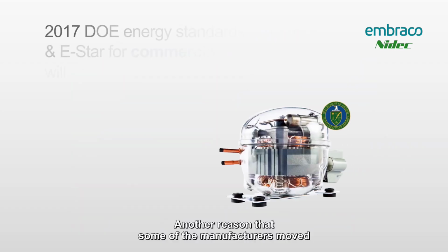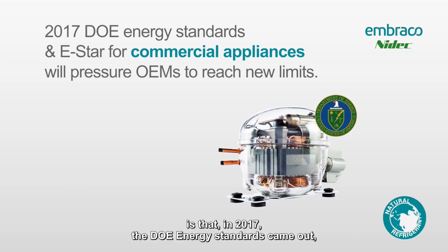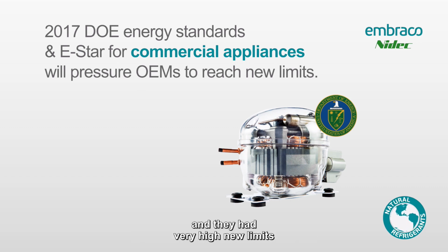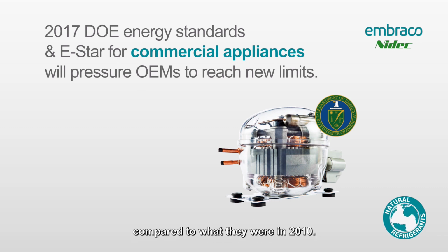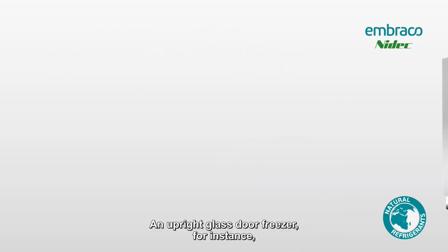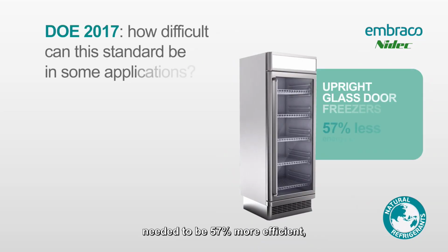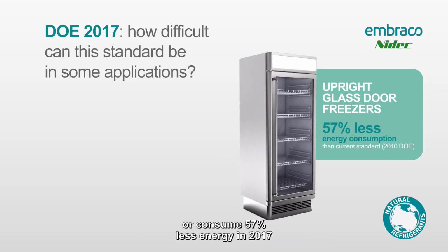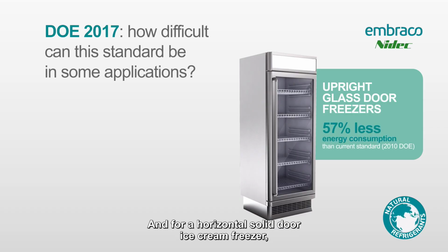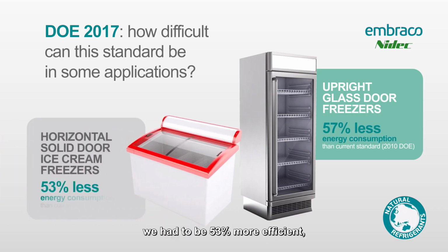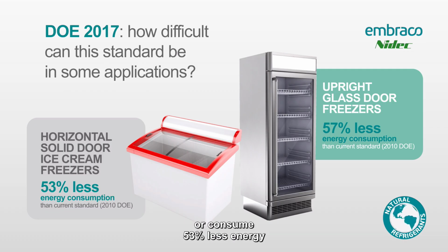Another reason that some of the manufacturers moved towards flammable refrigerants is that in 2017, the DOE energy standards came out, and they had very high new limits compared to what they were in 2010. An upright glass door freezer, for instance, needed to be 57% more efficient, or consume 57% less energy, in 2017 to meet those standards than it did in 2010. And for a horizontal solid door ice cream freezer, we had to be 53% more efficient, or consume 53% less energy than we did in 2010.